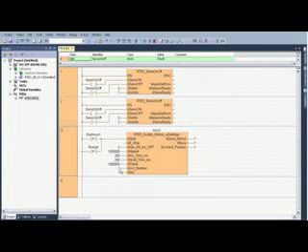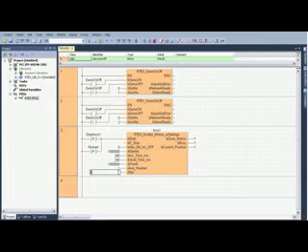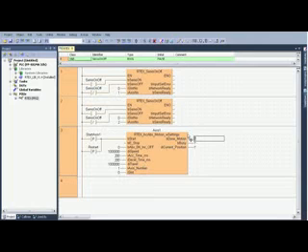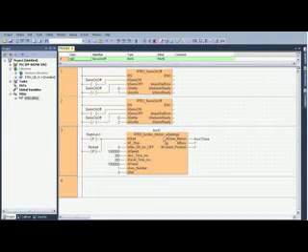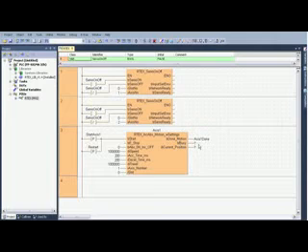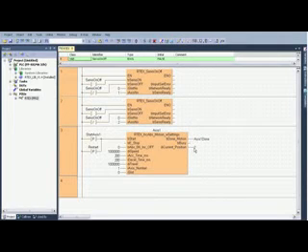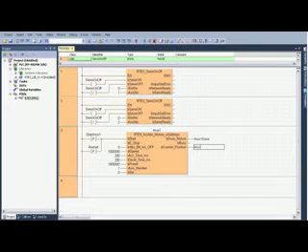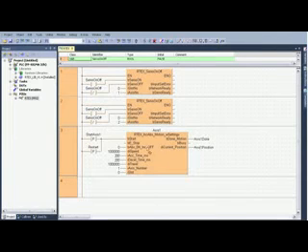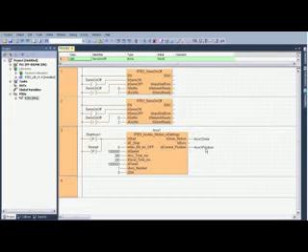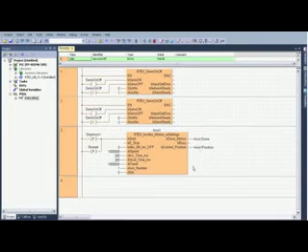And then once again I've got to tell it which axis we're working on and what slot we're in. Okay so on the output side I'm going to do something different here now. I'm going to use axis one done as my name. I'm going to create that. So what that'll do is once this is done rotating it's going to activate that. Busy I do not need, so I'm going to delete that. And then for visual's sake I'm going to create a name axis one position and that will update with the position of the motor as it's going. So once we start this moving you're going to see that increment and you'll be able to monitor it visually.